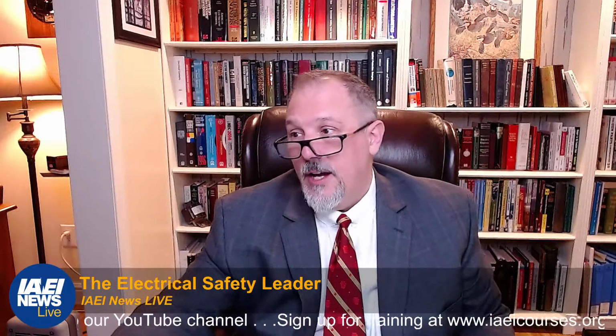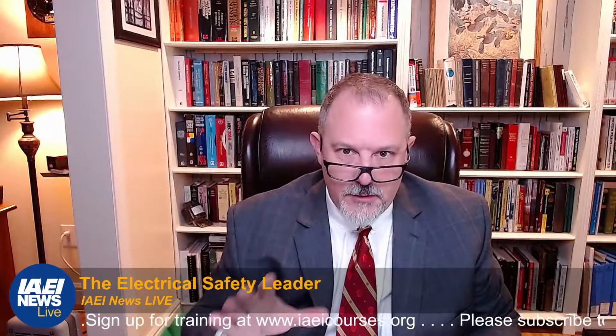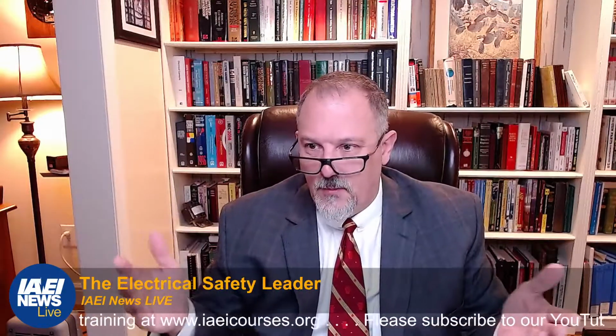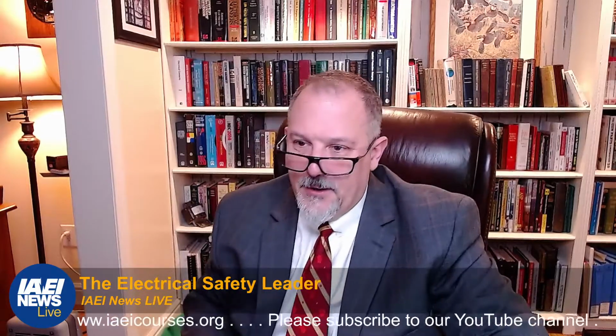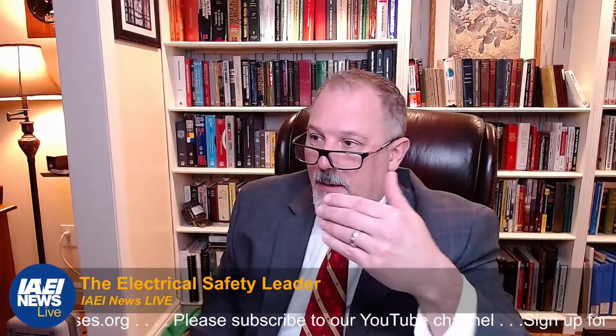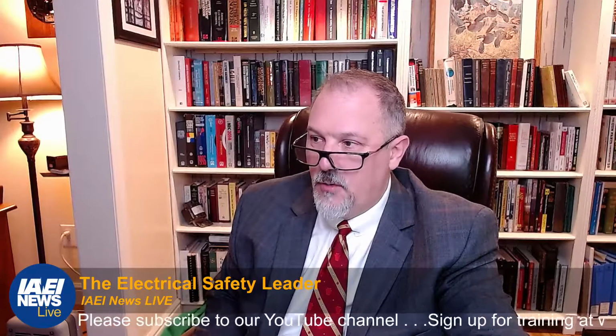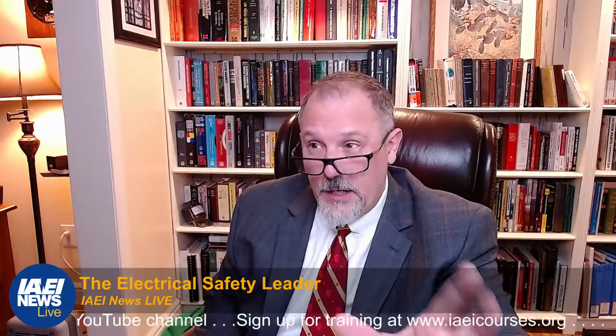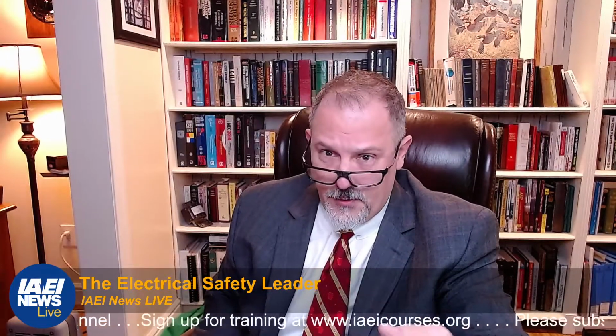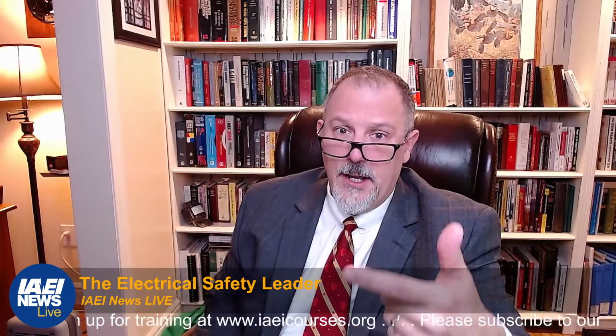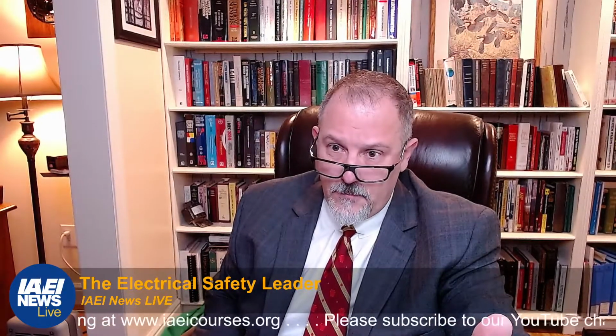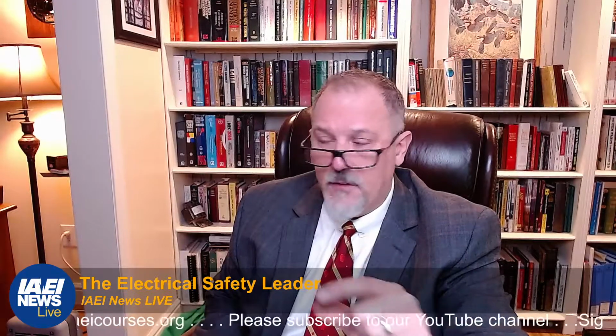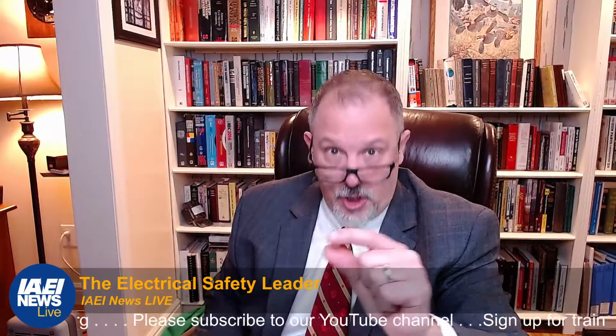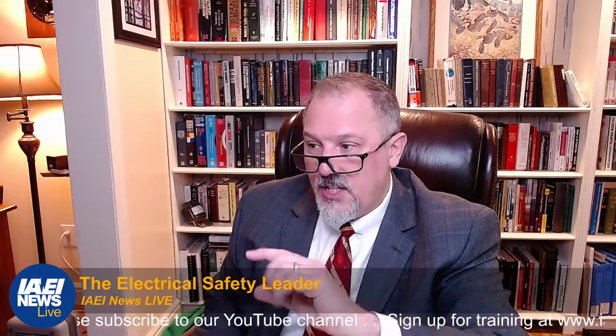110.14(D), so they made another change you're going to see, informational notes. For example, the first one, barrier and barricade, Mr. Snyder, yes. So arc flash hazard, informational note number 1 was rearranged. Here's another thing, if you read the NEC style manual, you have to go into it and read through it. The NEC style manual tells us how an informational note has to be constructed. So you're going to see many changes.